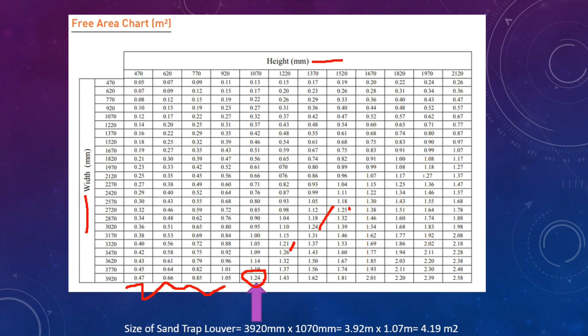The selected sand trap louver for this case is 3920mm by 1070mm — that is 3920 and 1070mm from the table. Converting to meters: 3.92m by 1.07m. Finally, the area of the sand trap louver for the 1200 liters per second case is 4.19 square meters.